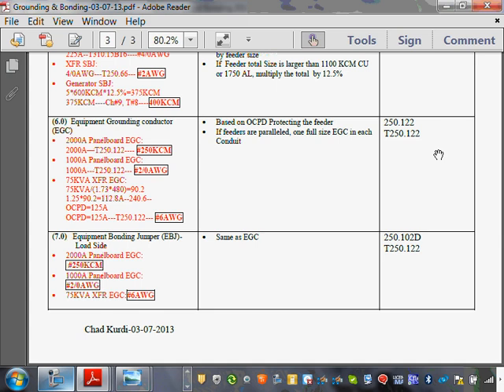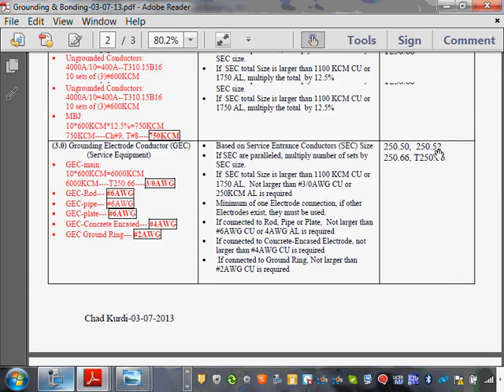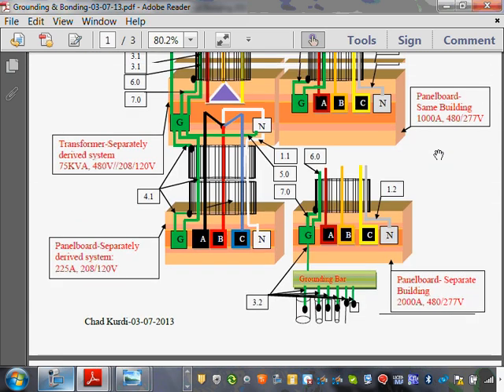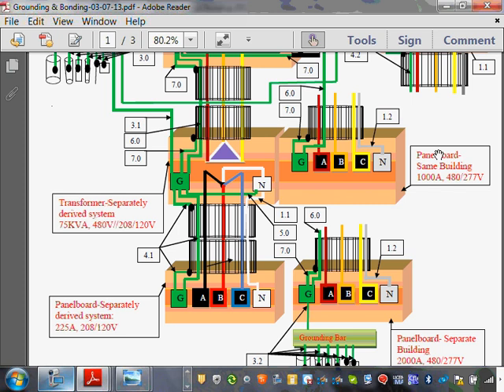Now the same transformer, guys, the equipment bonding jumper, it's called what? Same as the equipment grounding conductor. So the equipment bonding jumper on the load side of the transformer is the same, number 6. That's why we use the same wire. Come in, bond the conduit, the flex, and go inside the transformer. So that's for the equipment. That's grounding the transformer. So let's go back. Now that's exactly like any other panel, by the way. Up to this point, we really haven't done anything here. We just grounded the transformer.